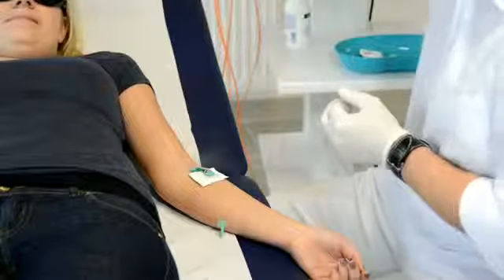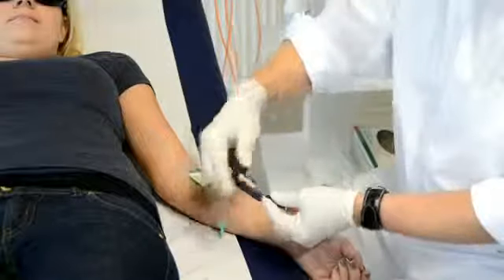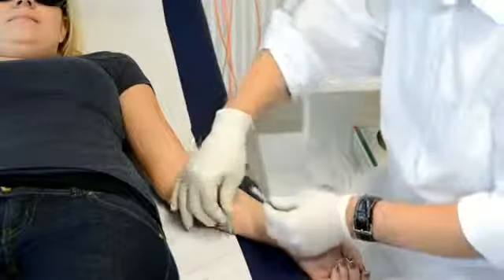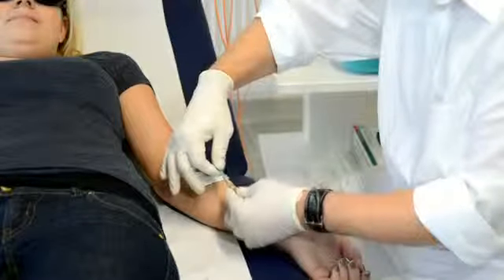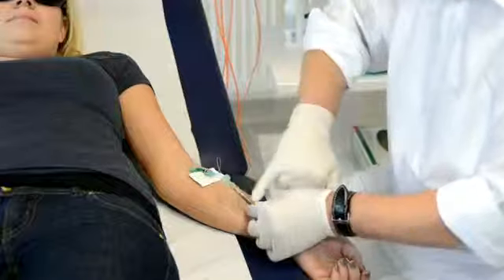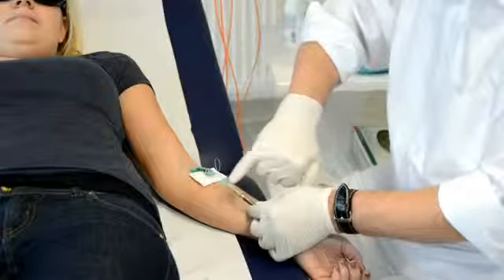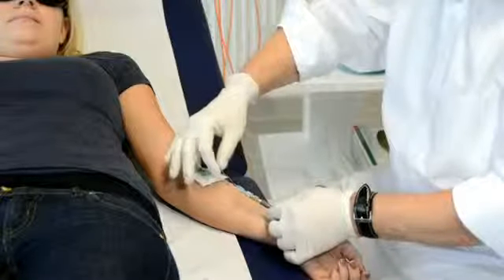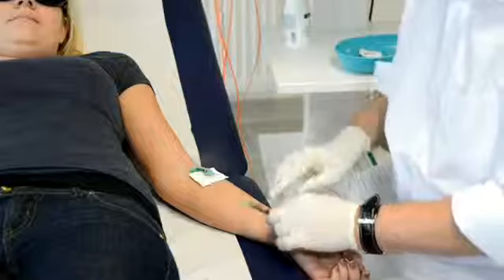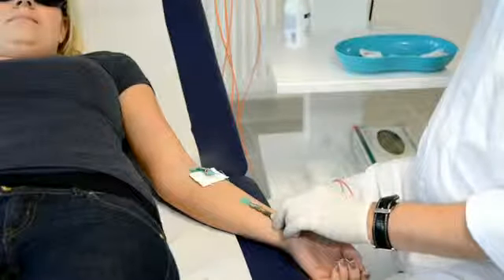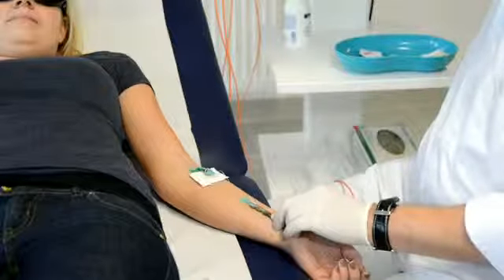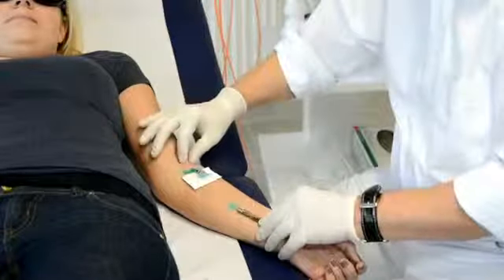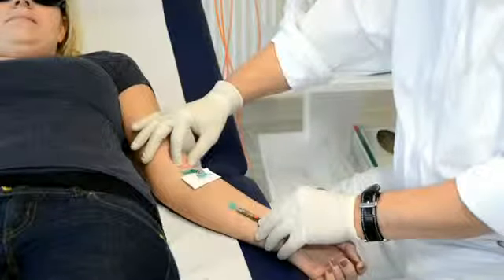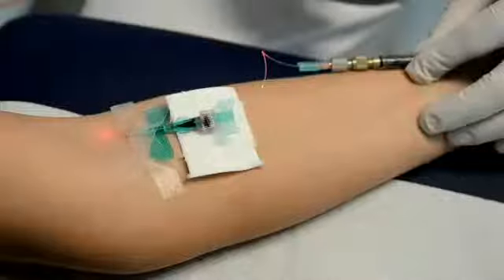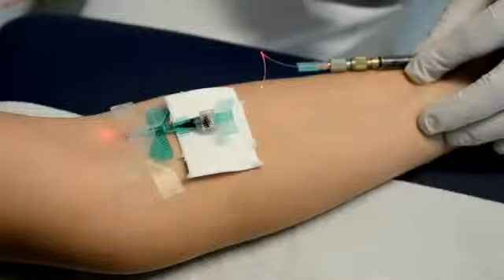I'm using in the first step the red laser, which has the glass fiber cable inside, and there's a special connector at the end of the cable in which I insert the end of the fiber optic catheter. The diameter of the glass fiber and the catheter is 0.4 millimeters only, and you see that we are using special glass fiber optics for the catheter from plastic material to make sure that never can break anything in the vein. So I switch the device on, and you can see how the red laser is shining through the skin. It's always an amazing effect for the patient, especially if you switch the light off.